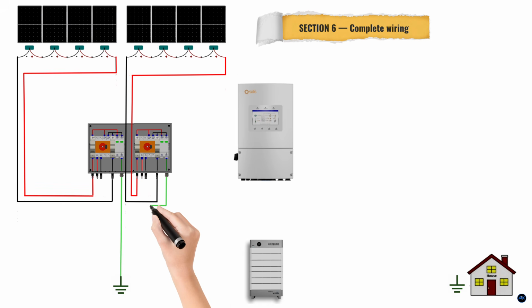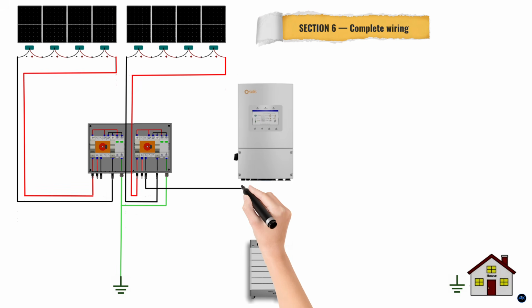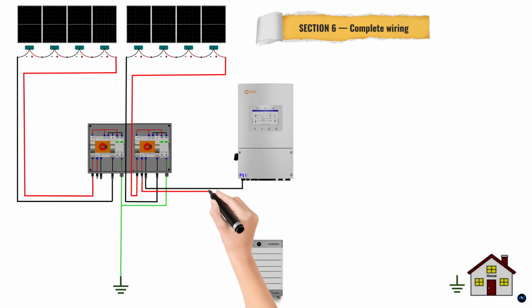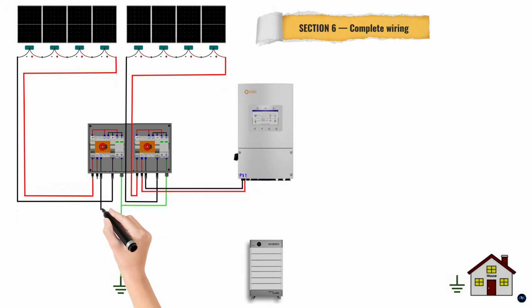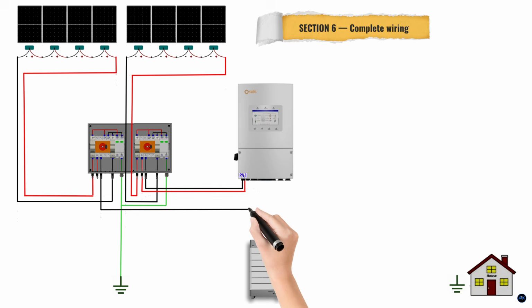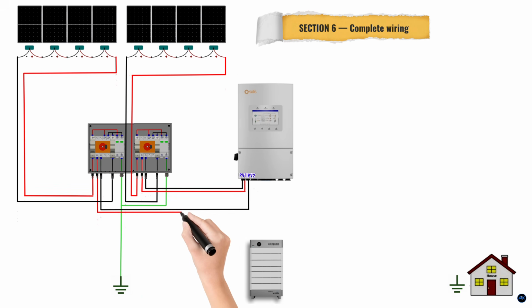Inside the IP65 combiner box, each string positive feeds through its own 20 amp DC fuse onto the combined positive bus bar. Both string negatives connect directly to the negative bus. The DC surge protection device connects across the bus to earth, guarding your inverter against lightning spikes. The DC isolator sits at the output, open until commissioning. Run 10mm squared cable from the combiner to the inverter's PV input terminals. Confirm polarity. Torque the terminals.